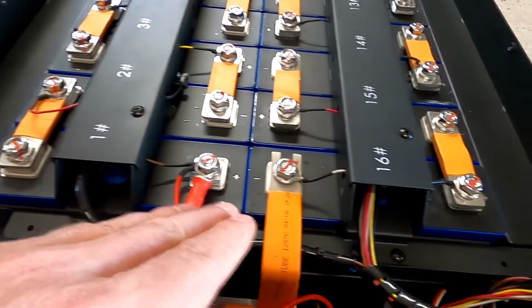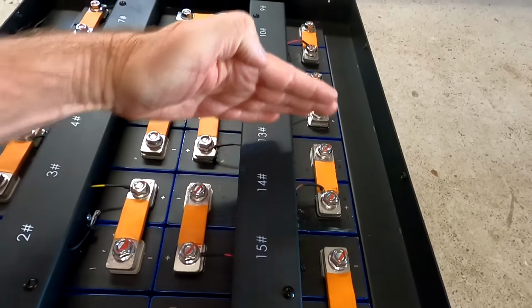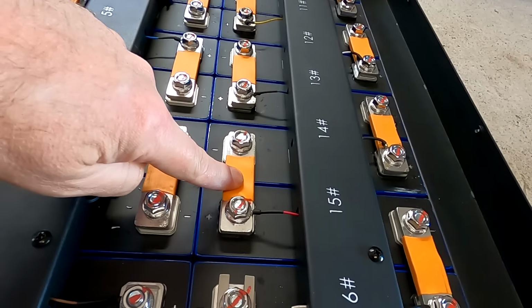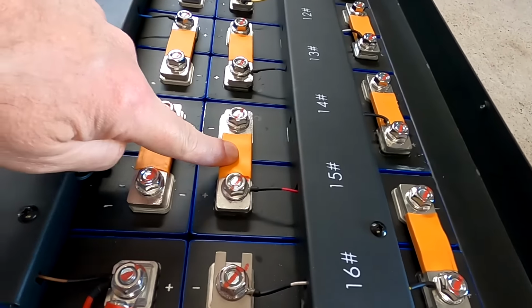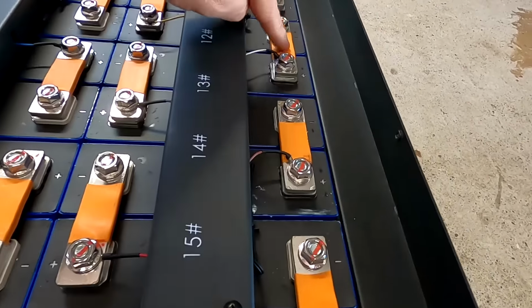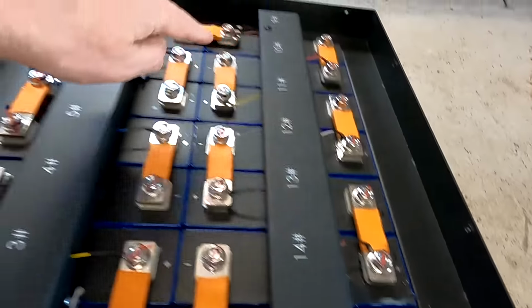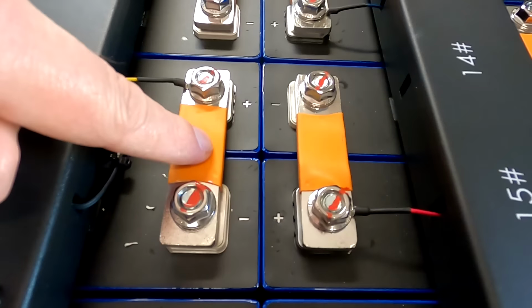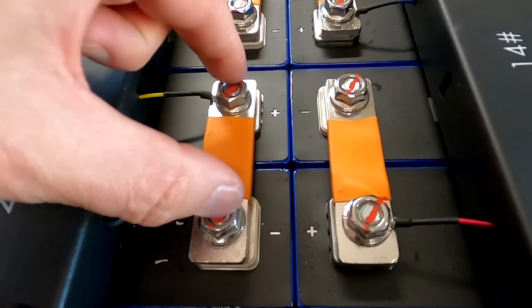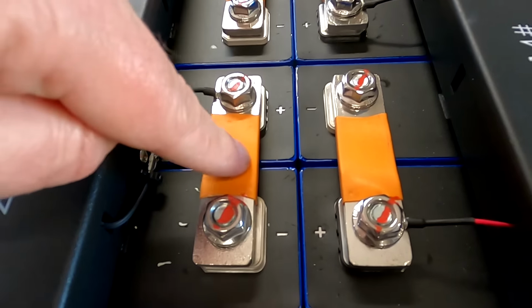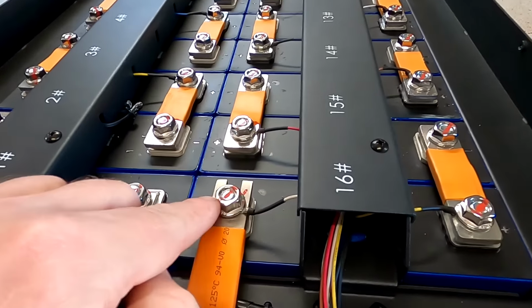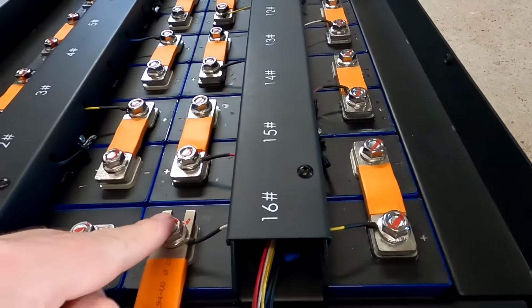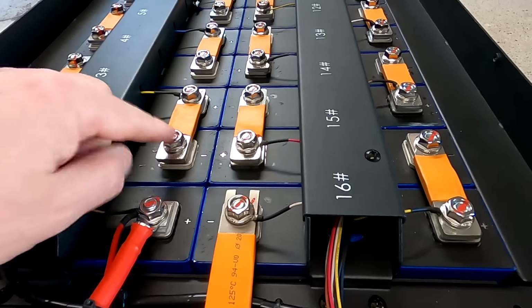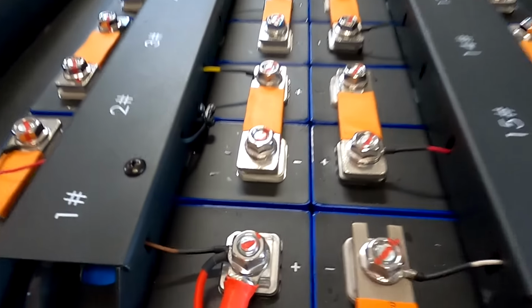We've got the front compression plate here, which compresses all the cells together. As in the small battery, we have flexible bus bars across the whole battery, so even if the cells expand or contract a little over time, these bus bars prevent any force on the battery terminals, which is really perfect. I also like that they've checked and marked all the screws in the battery, torqued down, checked, and marked with a red pen.